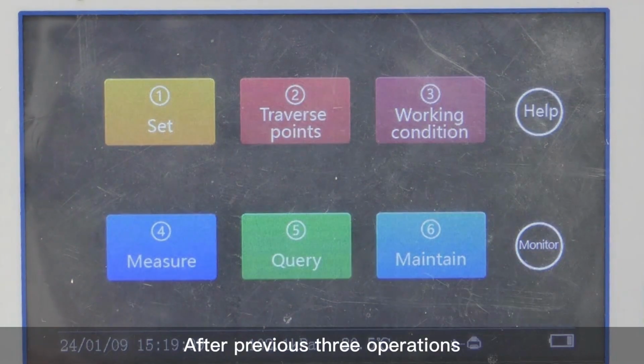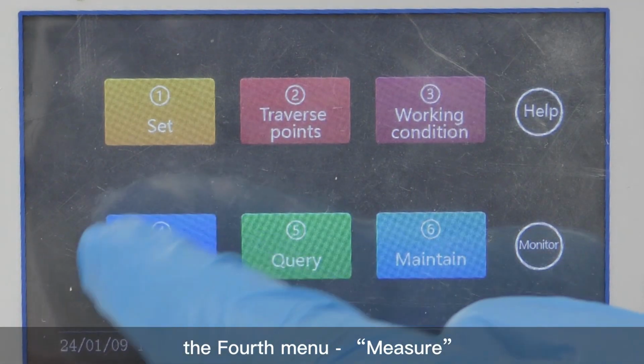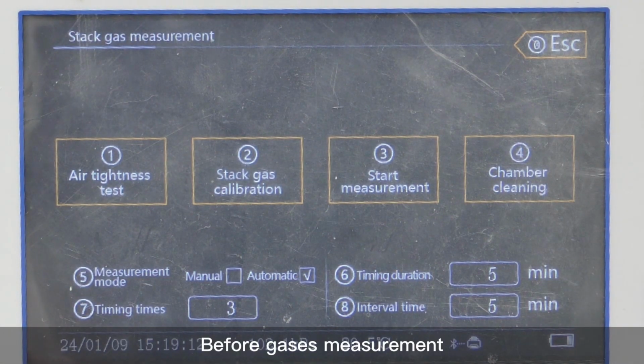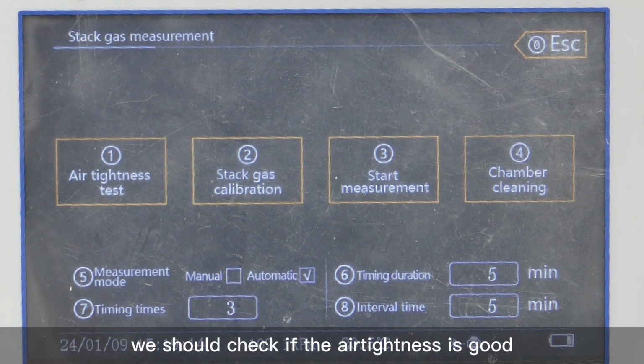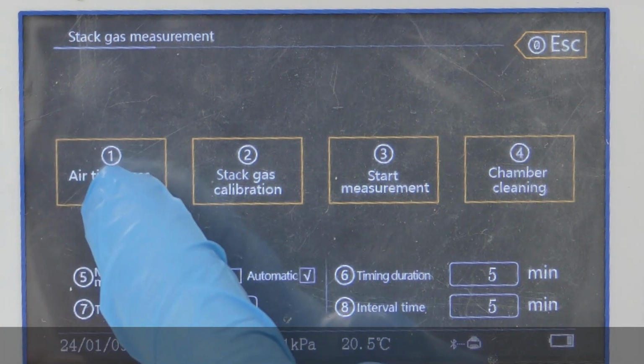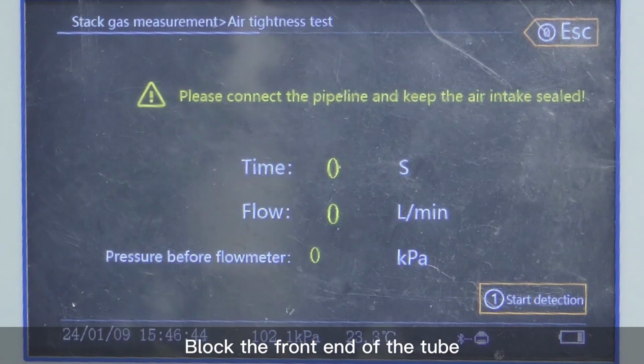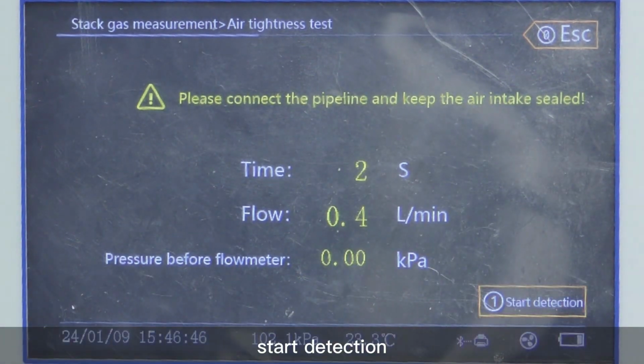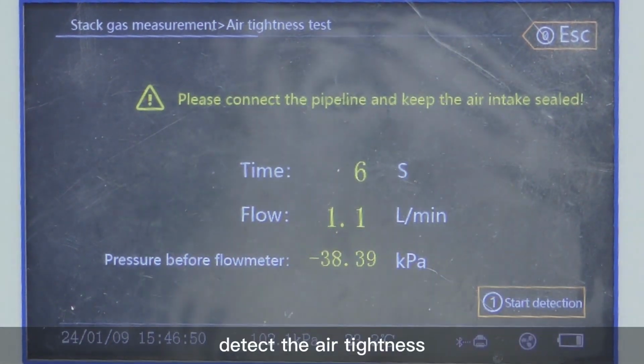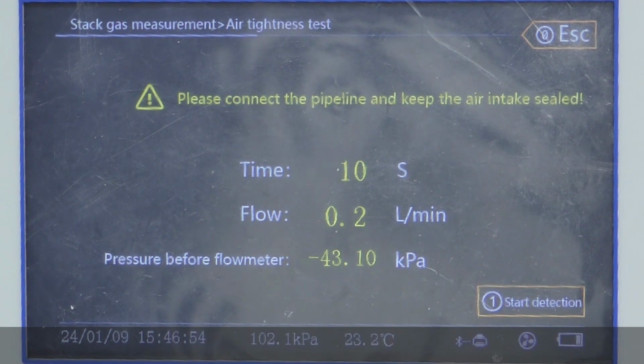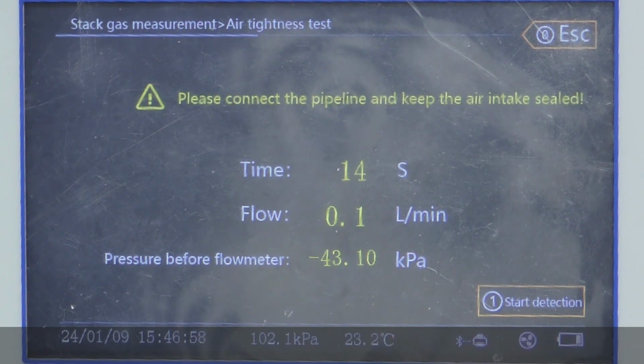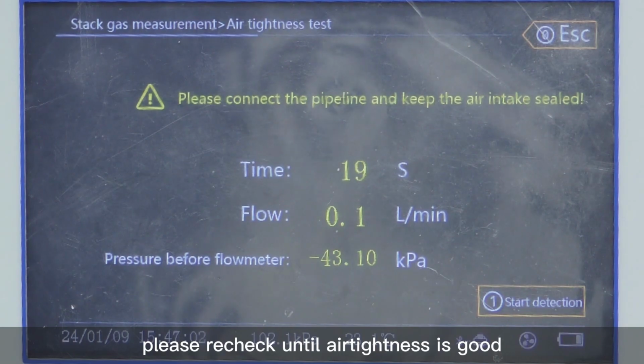After previous 3 operations, let's enter into the 4th menu, Measure. Before gases measurement, we should check if the airtightness is good. Block the front end of the tube. Start detection. The analyzer will automatically detect the air tightness. If it shows air leakage, please recheck until airtightness is good.